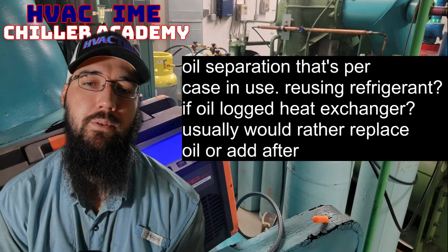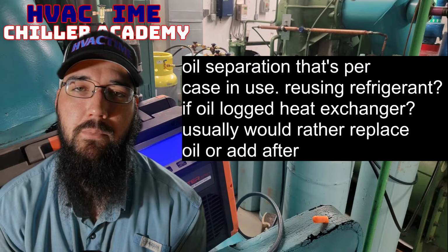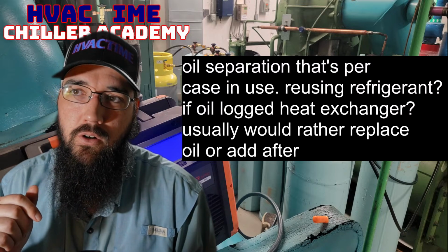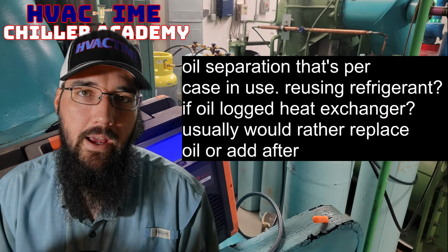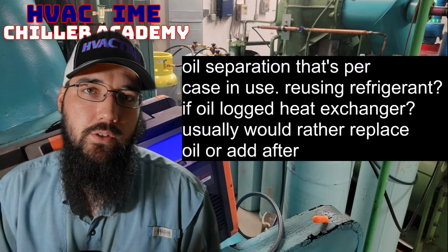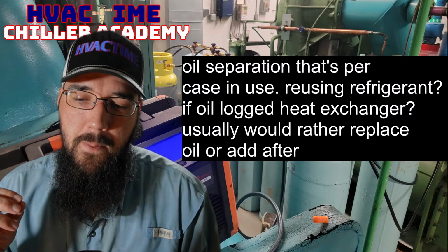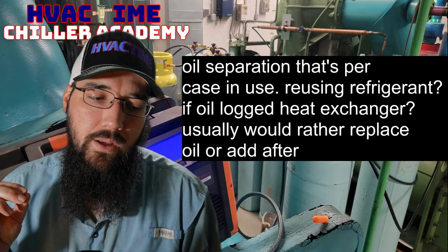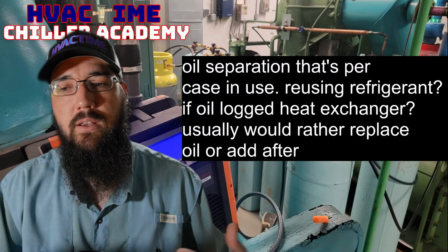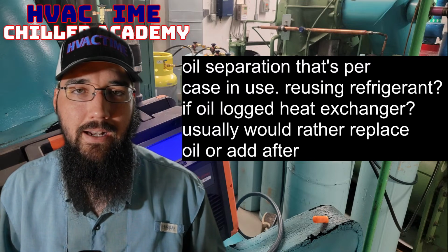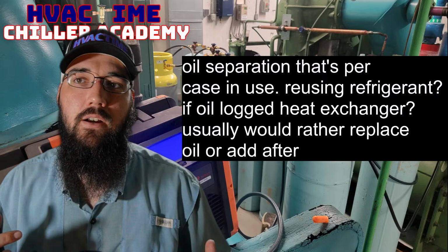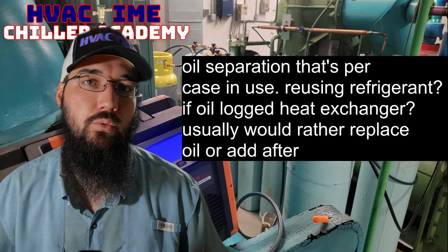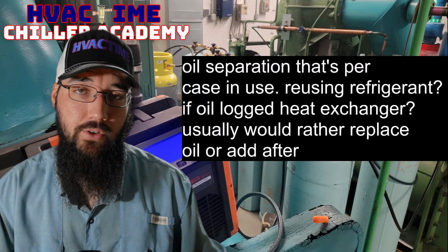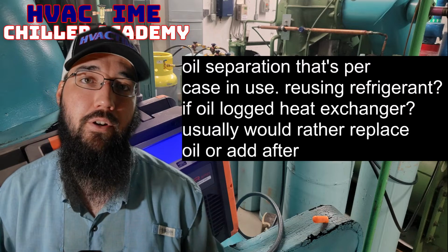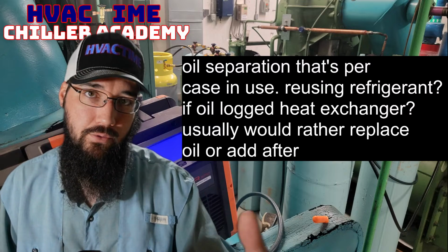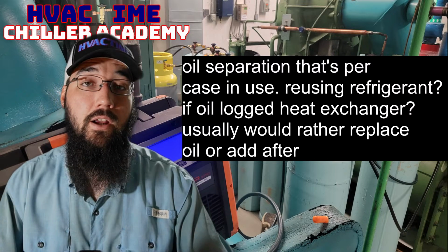But let's give an example of a situation like this: an RTHD, those are horrid at oil migration. It's a water-cooled screw chiller, and if the machine isn't online and I can't get the compressor running to recover that oil first, that means all I have is in the evaporator and it's stuck there. I'm going to go through that procedure I talked about earlier.